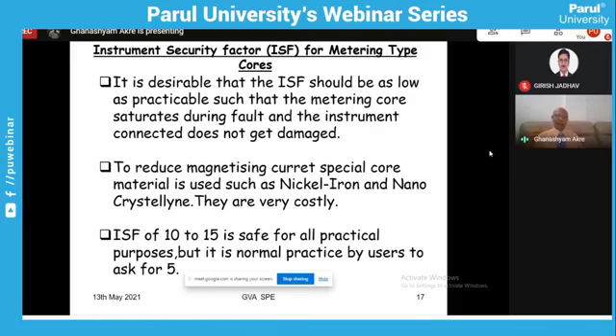Similarly, for reducing the magnetizing current, special core materials are used, such as nickel iron and nanocrystalline. I have told you that toroidal cores of CRGO material will draw excitation current or magnetizing current, and that will produce the error. Now, nowadays we are required to produce 0.2 S class current transformers for tariff metering in Gujarat and throughout India. This 0.2 S class as per IEC indicates that your error should not be more than 0.2%. This is very, very delicate, and that is why normal CRGO, that is cold rolled grain oriented iron, may not give that low a current, and that is why a nickel iron core or nanocrystalline core are nowadays used. They are very, very costly, maybe about 10 times costlier than CRGO, but as a special purpose, they are being used today.